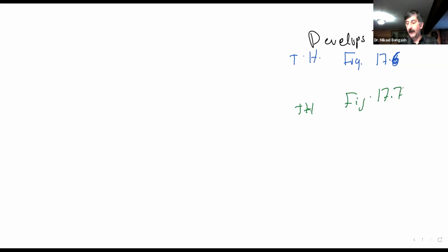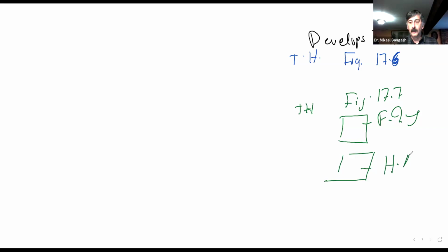Here I have two images on top of one another, right? First, we have a regular fundamental image, where the bottom one is going to be a harmonic image. What did we mean by a fundamental image? That it was produced by a regular main fundamental frequency, or main frequency, or resonant frequency.